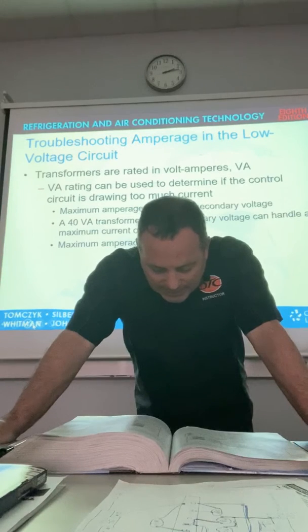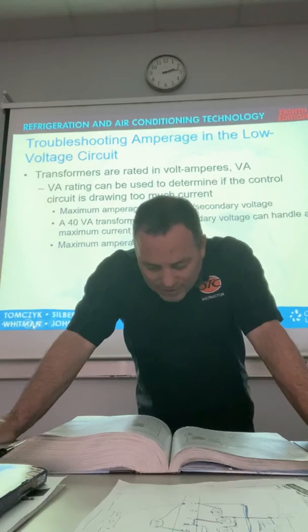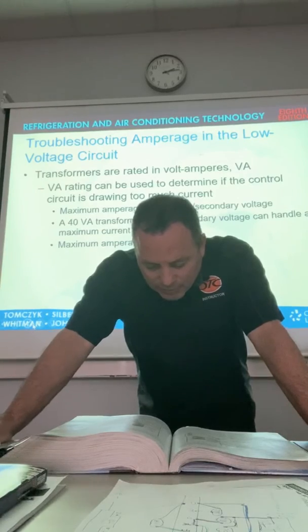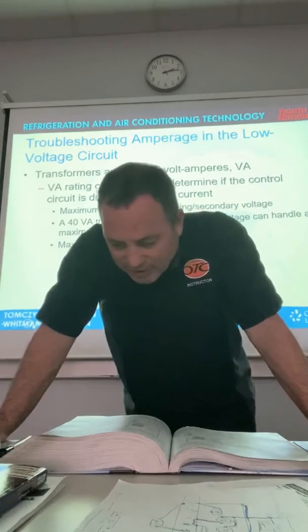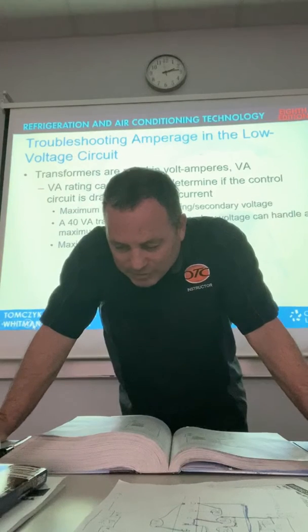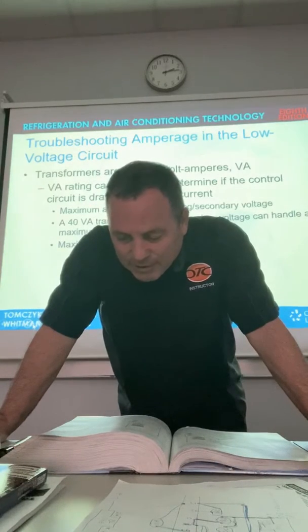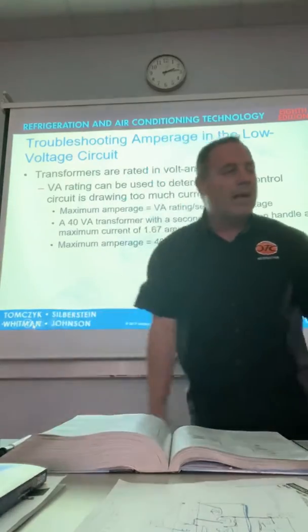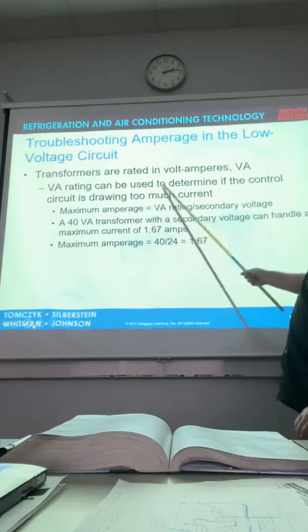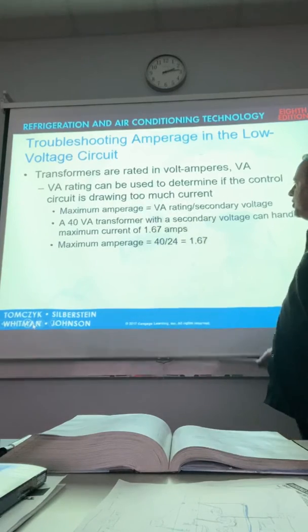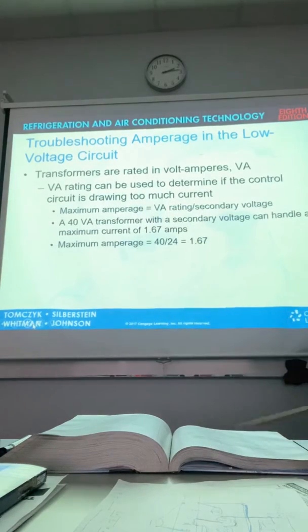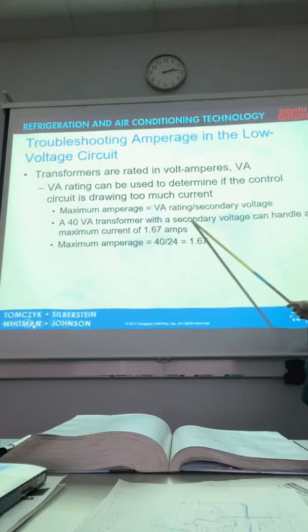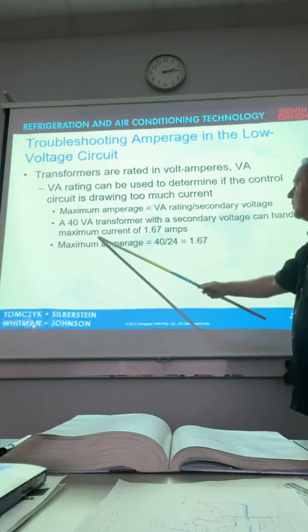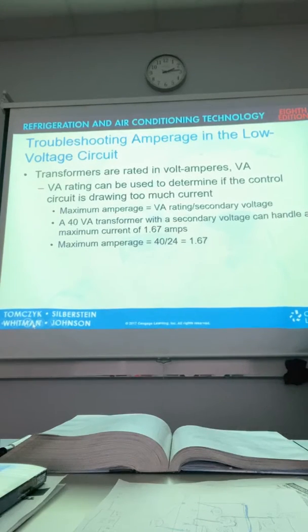It's commonly called VA. The rating can be used to determine whether the transformer is underrated or drawing too much current. For example, it's quite common to use a 40 VA for the low voltage power source. This tells the technician that at 24 volts, the maximum amperage the transformer is expected to carry is 1.66 amps. So how do they get that? The VA rating can be used to determine if the circuit's drawing too much current. Maximum amperage, okay? A 40 VA transformer with a 24 volt secondary voltage can handle a maximum current of 1.67.